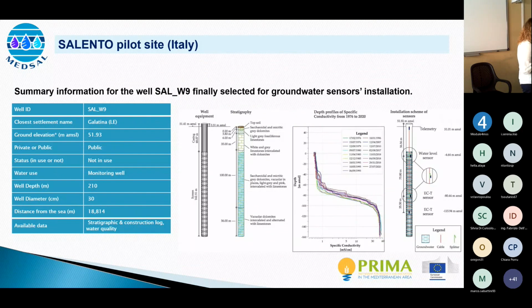After a few months, Alessandro had the possibility to verify that the signal was probably disturbed by many factors, and during a maintenance operation, we had the possibility to check that the sensor was corroded, subjected to the high salinity of the water.